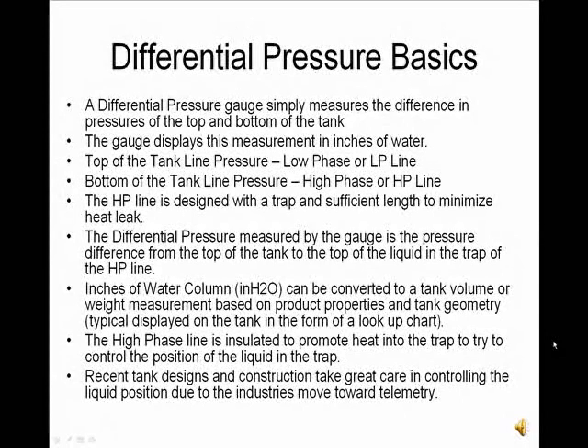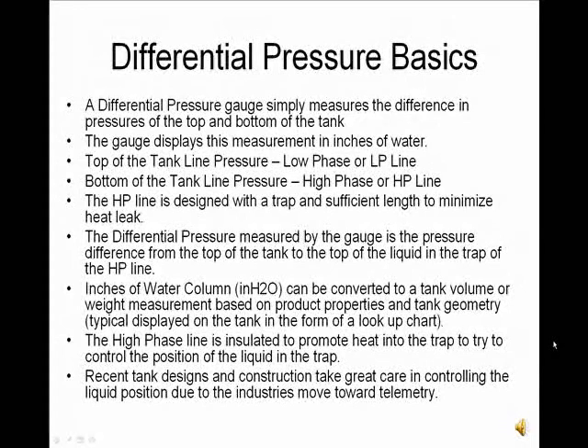The HP line is designed with a trap and sufficient length to minimize heat leak. The differential pressure measured by the gauge is the pressure difference from the top of the tank to the top of the liquid in the trap of the HP line. Inches of water column can be converted to tank volume or weight measurement based on product properties and tank geometry, and is typically displayed on the tank in the form of a lookup chart.